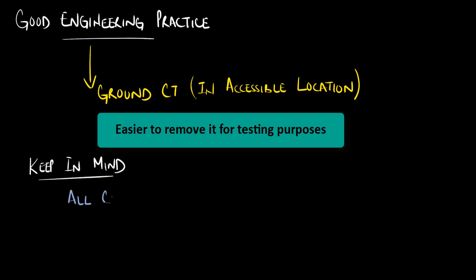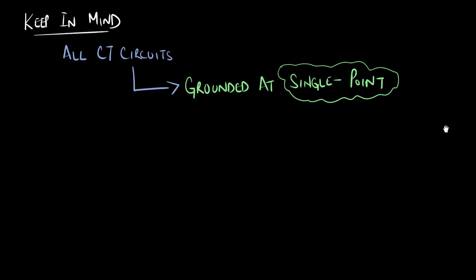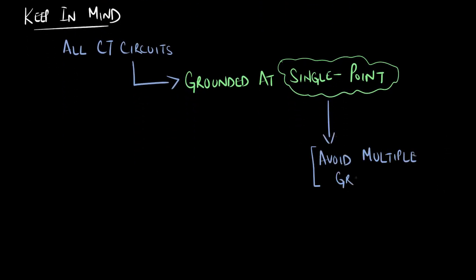Keep in mind that all current transformer circuits are to be grounded at a single point only. This is to avoid the occurrence of multiple ground loops, which can cause the relay connected to the secondary winding to trip under false conditions.